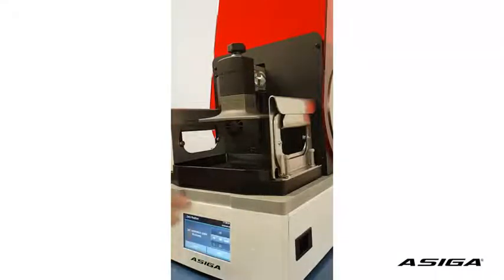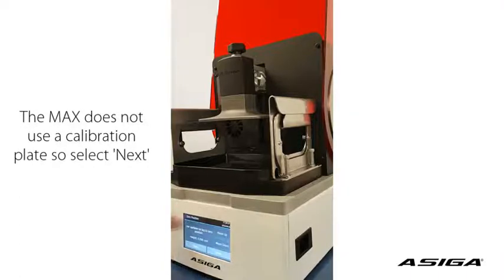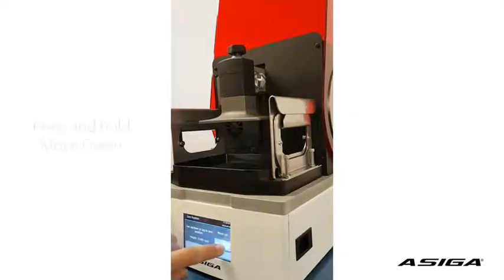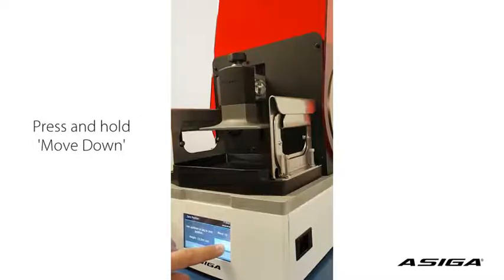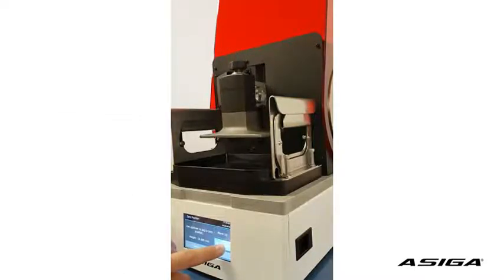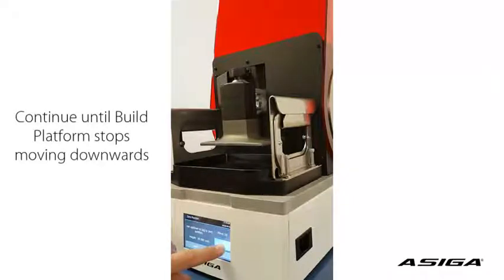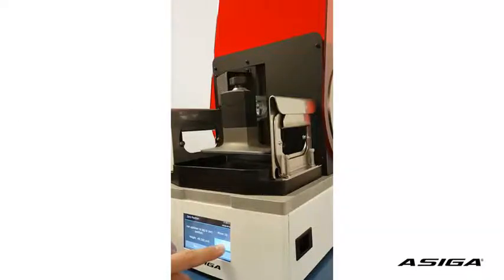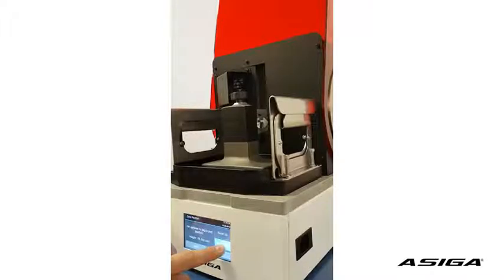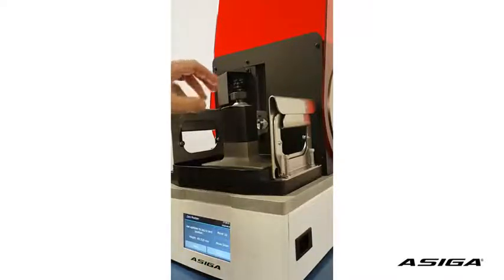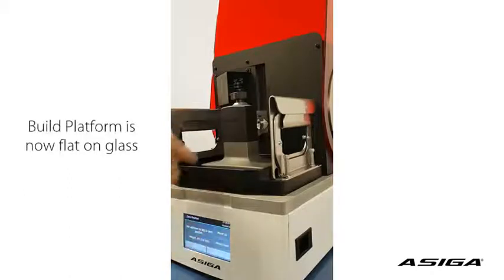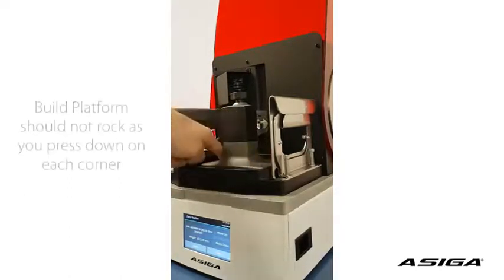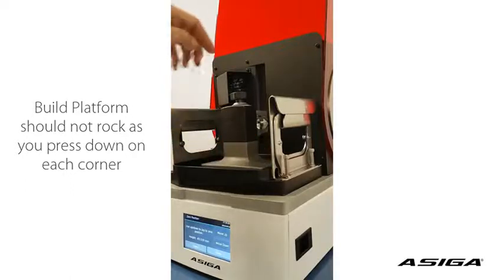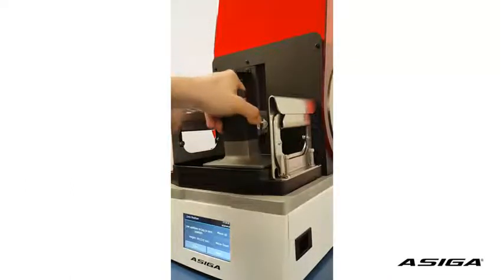Now we click OK. We don't have a calibration plate, so we don't set a calibration plate thickness, and we move down until the axis stops to move. So the axis stopped to move. We can't move further down. The platform is lying flat on the glass. This is important, so it's not tilting or rocking. And we still have a little bit of play when we lift the platform.